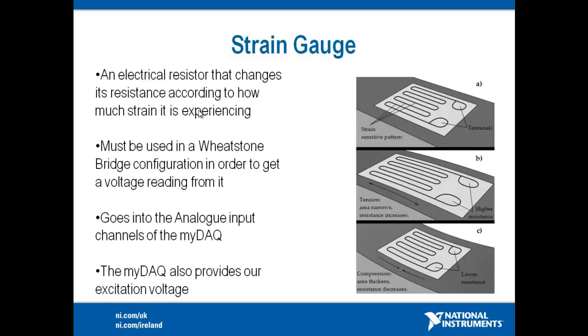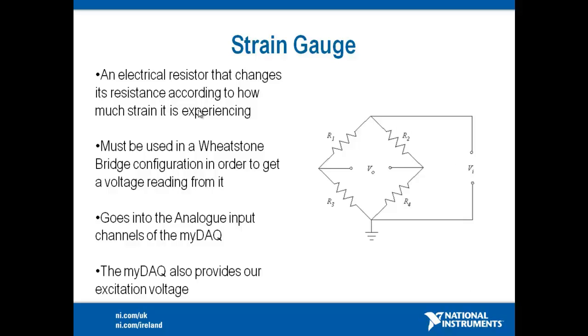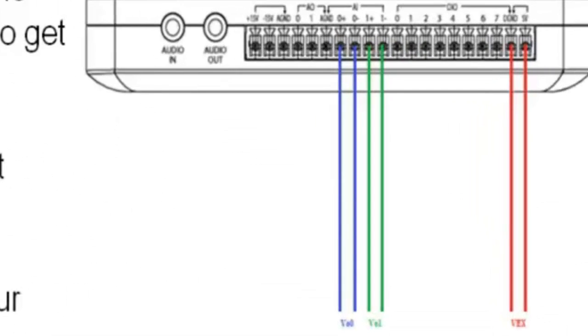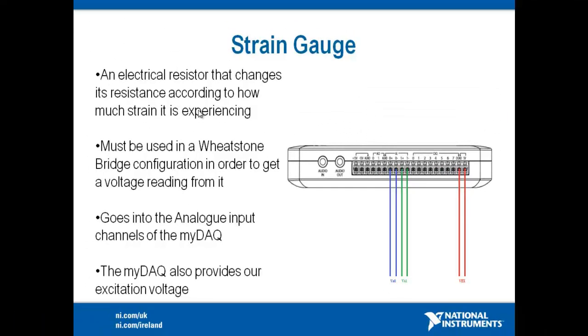So a strain gauge is basically an electrical resistor, which varies depending on how much strain it encounters. By putting it in a Wheatstone bridge configuration, we can measure the imbalance that this bend causes as a voltage. This voltage can then be passed into the analog input channels of our myDAQ, where it can be translated to our computer. The myDAQ also provides an excitation voltage to this circuit, which is essential in generating the voltage which we're eventually going to read.